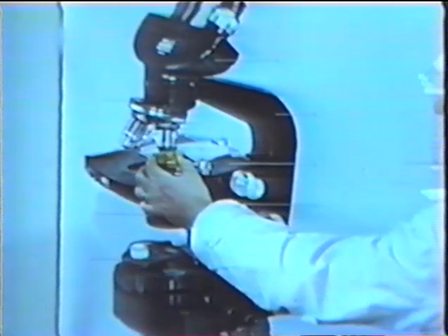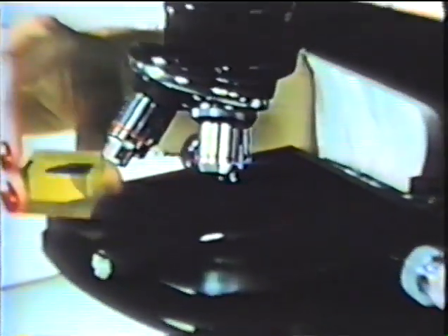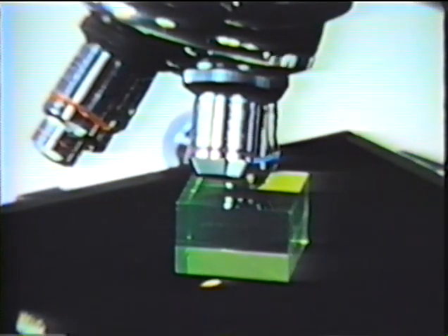In our stretched path of the rays, we have correspondingly the lamp with collector, the illuminating apparatus, the plane of the specimen, and again the combination of objective and eyepiece. In order to explain still more clearly what happens in the specimen plane, we place a fluorescent glass cube between condenser and objective. This allows us to follow directly in the microscope how the light beams run at this position. The cone of rays becomes more obtuse or more acute — narrower or wider — depending on the manipulation of the aperture stop.